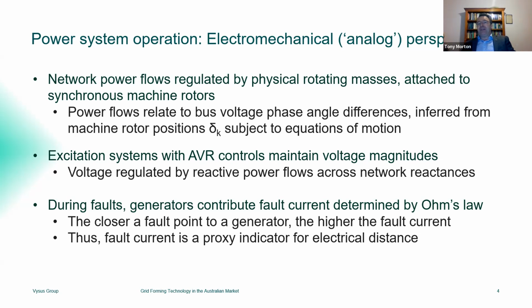We basically look at the EMF of each machine, we look at the impedances of the network, and we do a very basic network calculation, essentially Ohm's law, that tells you how much fault current you get at any particular location. And the fault current that you get there is in fact a proxy for the electrical distance of that fault point to each of the generators. And that is what has made short circuit levels, fault levels, short circuit ratios, whatever you call it, a useful measure of system strength, because it acts as a proxy for that electrical distance.